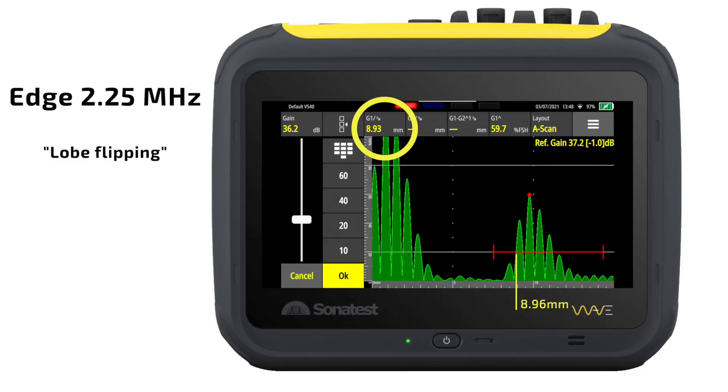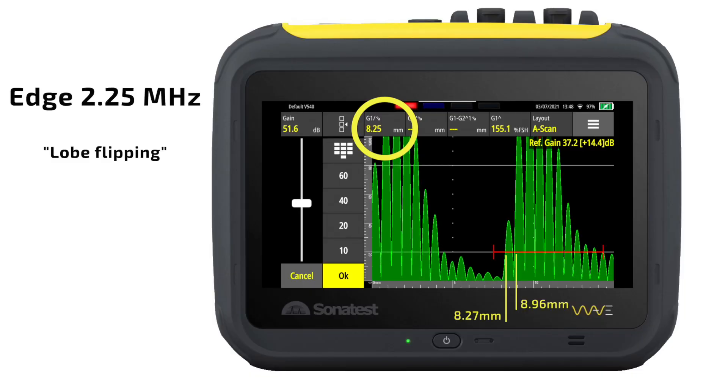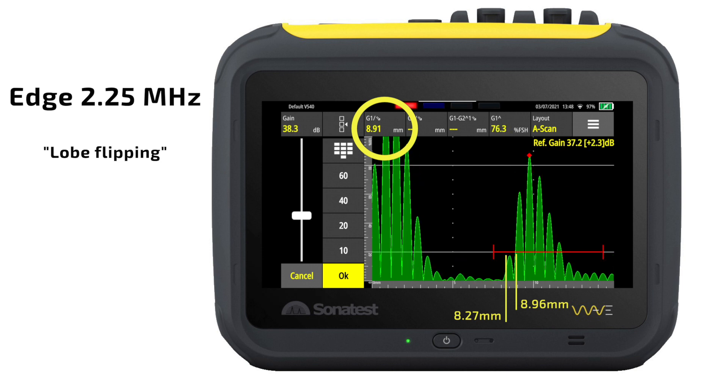Another thing that can go wrong is lobe flipping or lobe switching. An A-scan in its natural state has negative and positive lobes. In order to get the most accurate and repeatable readings, you should be taking them on the same polarity lobe each and every time. But because we're usually using a fully rectified signal, we can't tell which one is which. It's very easy with just finger pressure or gain to literally push an earlier lobe up, trip the gate, and change your reading. On a 2¼ MHz transducer with the gate mode set to edge about halfway up the waveform, if we raise the gain we can get a change of about 0.5 mm or 20 thou. This difference in error when you switch lobes will change depending on the amplitude of the signal if you're using edge.